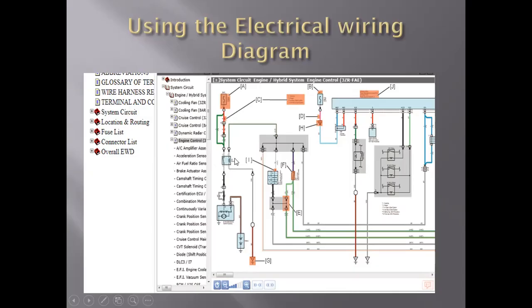So if we notice, this relay is in series with the rest of the circuit. So if for instance there's a problem in any circuit and you can find the relay for that circuit, it's much easier to execute the test right there. Because you'll save a lot of time, since you're checking the circuit from the middle. When you check the problem from the middle of the circuit, it tells you whether the problem is upstream or downstream.